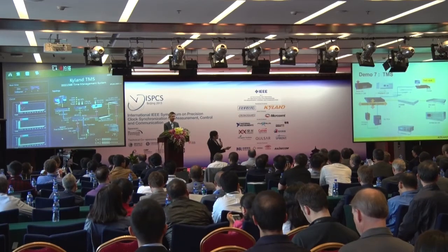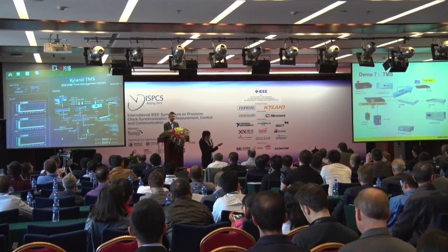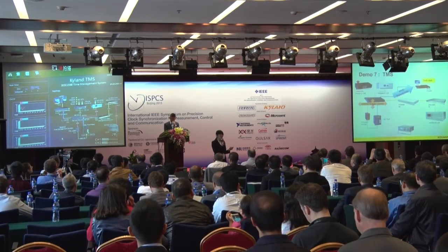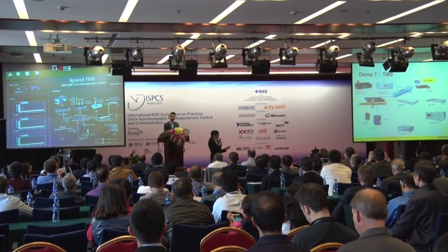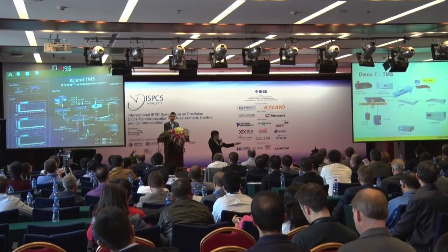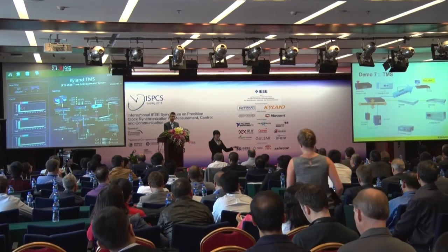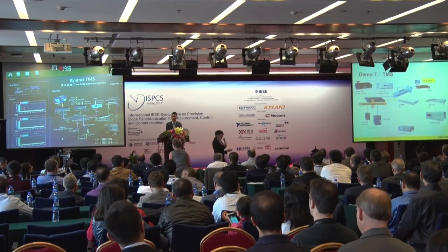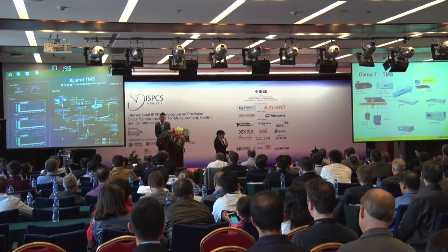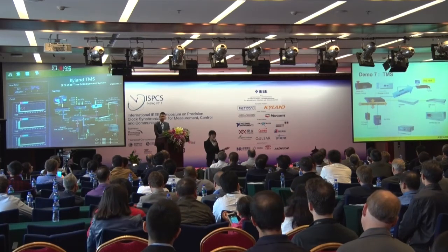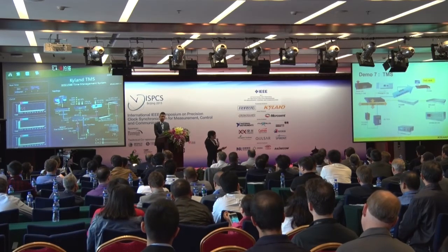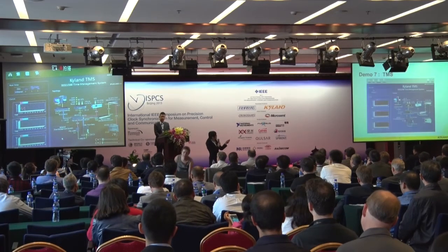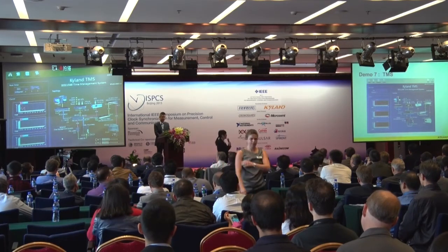So anyone who subscribes to this information can send out the MMS report with SOE information inside. We are using a data analyzer to concentrate and analyze all these MMS reports from the end devices, and we can use an HMI through this data analyzer to track the node time in the system. And that's how this TMS works. And then this is how the TMS HMI really looks.